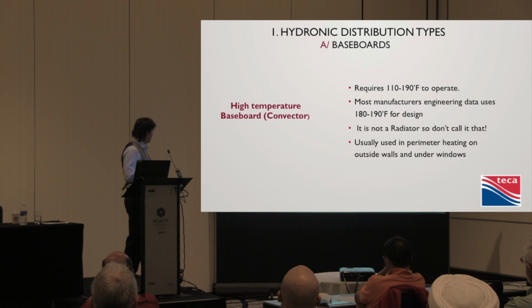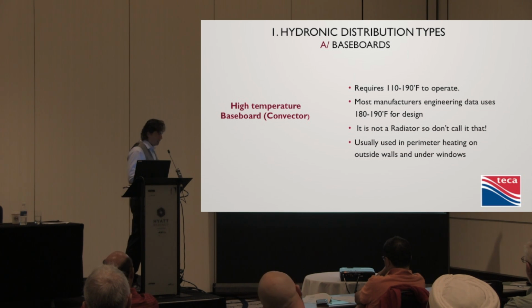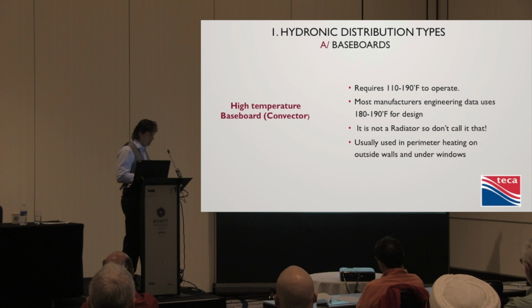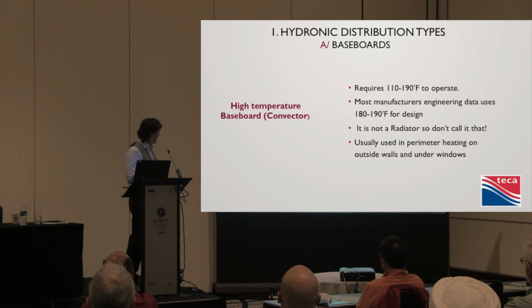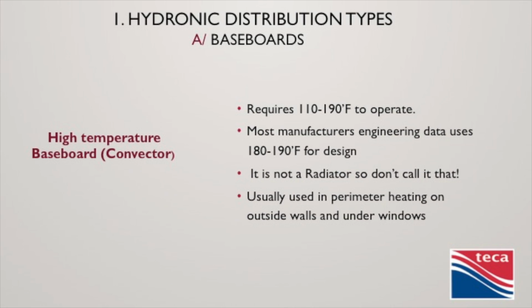High temperature baseboard convectors. Okay, they require 110 to 190 degrees F to operate. At 110, they're pretty much doing nothing. At 190, that's actually, if you look at the engineering data, they size the things at either 180 or 190 degrees. So that's hot water. And forgive me if I talk Fahrenheit here. We can switch to Celsius at some point, but it's uncomfortable for me. So all of the design criteria is around 180 degrees. So it's smoking hot water. So would we use a condensing boiler with a baseboard system if we had to run that all the time? The answer to that is no. Condensing boilers want to run cool to be efficient.